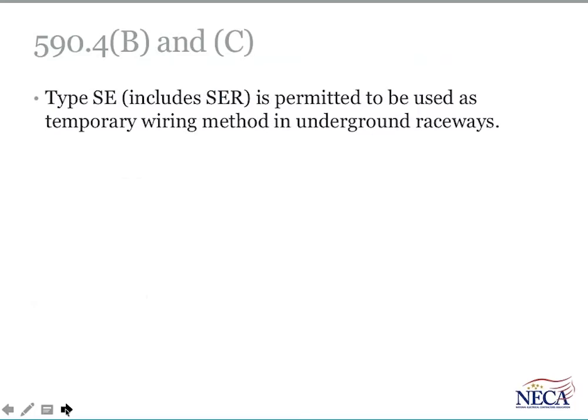The thought process here is that while SE and SER are not permitted in permanent installations, they certainly can serve well in an underground raceway during the period of construction because they're required to be removed once the construction is complete. So Panel 3 acted favorably to allow it because there's a time restraint on it.